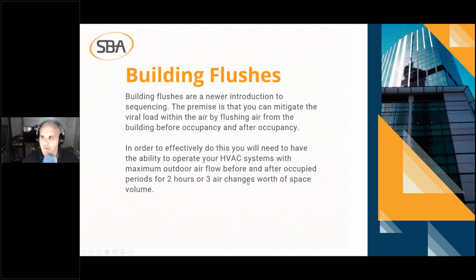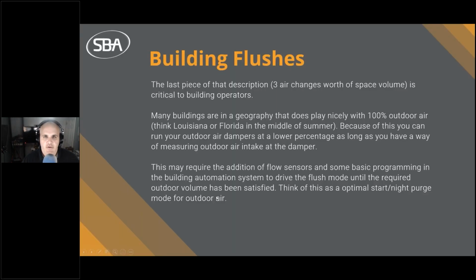That's a very important thing to note because as we start to concern ourselves with outdoor air humidity, this 3 air changes worth of space volume will help us find some ways to get around that humidity that we may be bringing into the building. So you need to be able to operate your HVAC systems with maximum airflow before and after these occupied periods, or we can implement a sequence that gets us 3 air changes worth of space volume prior to occupancy and post occupancy.